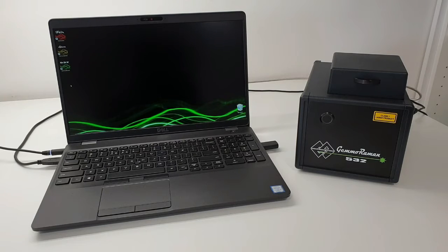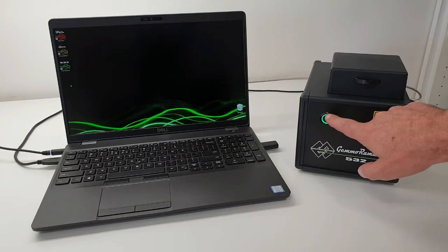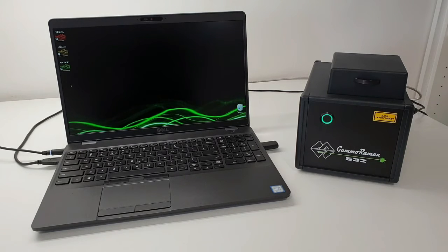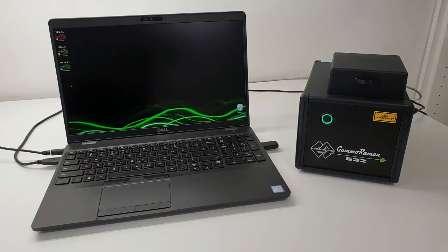Manual acquisition. The GemmoRaman can be operated even in manual mode. The autoscan procedure includes all the steps needed to automatically identify the stone under testing. All these steps can even be performed manually, and very often there are good reasons for doing that.